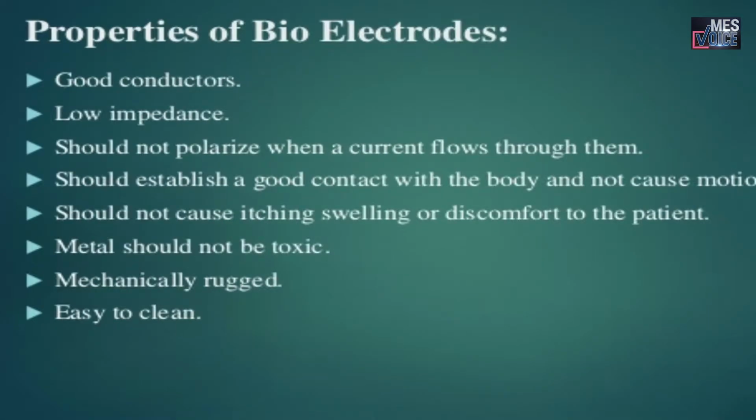Next we will see properties of bioelectrodes. Bioelectrodes are good conductors with low impedance, and should not polarize when current flows through them. They should establish a good contact with the body without causing motion, and should not cause itching, swelling or discomfort to the patient. The metal should not be toxic, and should be mechanically rugged and easy to clean.